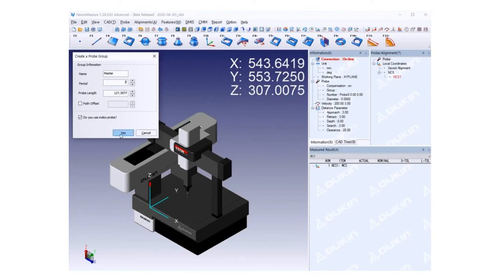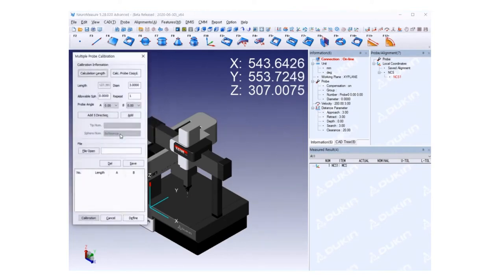And then click OK, and then as you can see, the multiple probe calibration window will pop up, and then you can see all these options. But right now I'm going to show you how you can adjust the A angle and the B angle. As you can see, 7.5 degrees, and then you can change anything you want. And then first, the probe should be 0 degree of A and B. And you can delete it just like that.